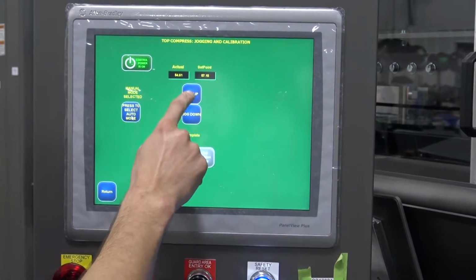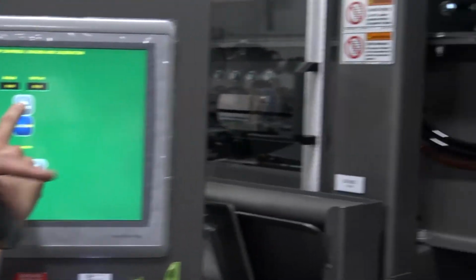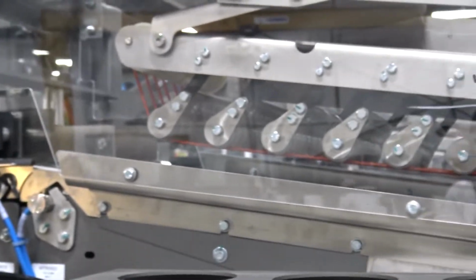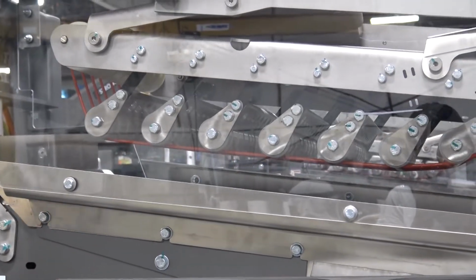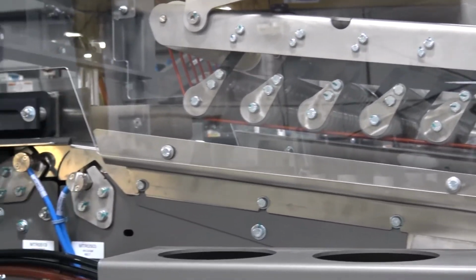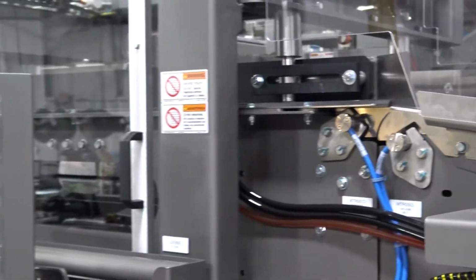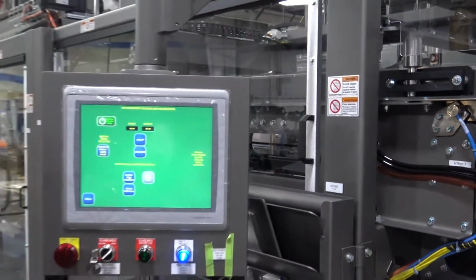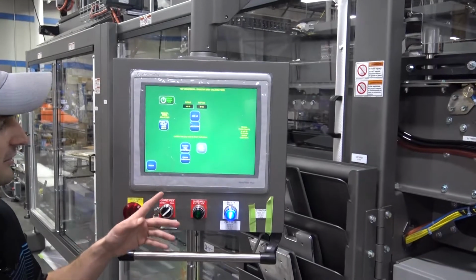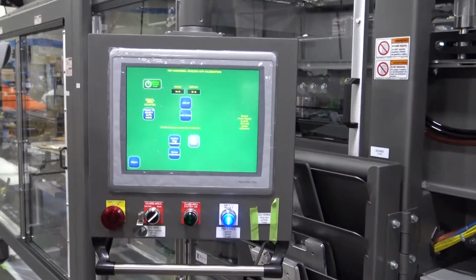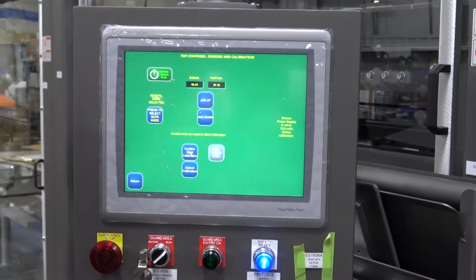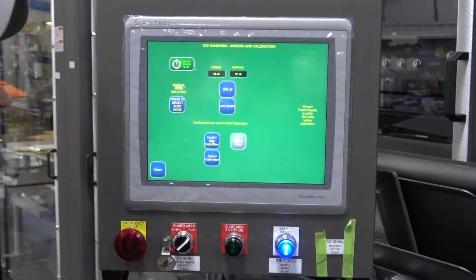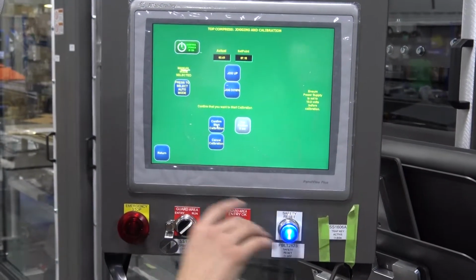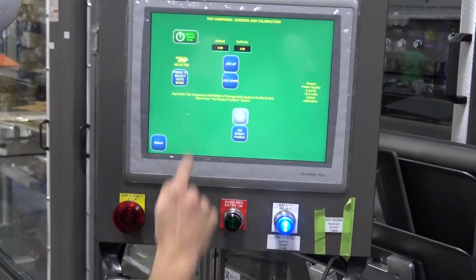Here I get my jog buttons. I can jog this axis up and down and make sure that actuator is working in the first place. So it is. And now I want to start the calibration procedure. So start calibration. Confirm you want to start calibration. You get a message saying remove change parts prior to the calibration. It's not really necessary in this case. There's no change parts interfering, so we're going to go ahead and confirm start.